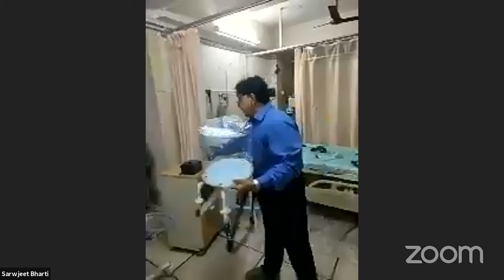Now, none of these interfaces is a supplement to a ventilator per se, but they can be used in a setting where we don't have a ventilator available, by making use of these ward outlets, which have 15-liter flow. If you have a Y connector to this, you can give 30 liters of flow. Or if you have a high flow meter device with you, you can go up to 60 liters. And this can be used if a ventilator is not available, to tide over the crisis. We can use them with a BiPAP machine, with high flow oxygen, or with the old generation CPAP machines.